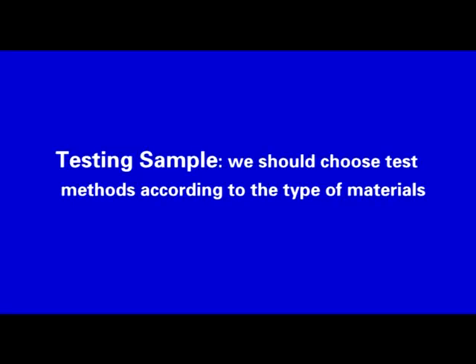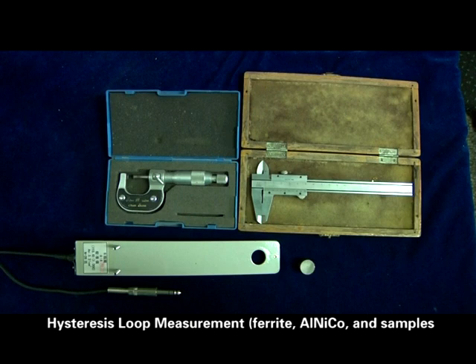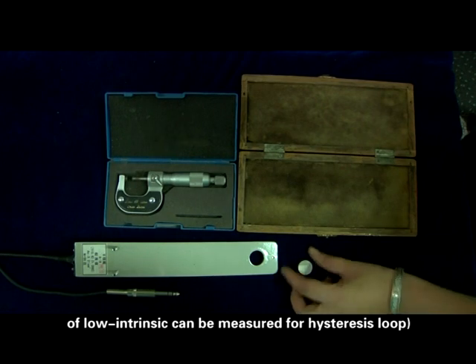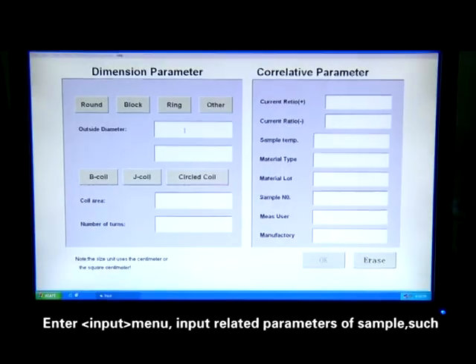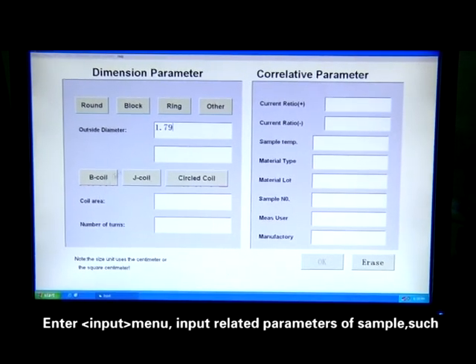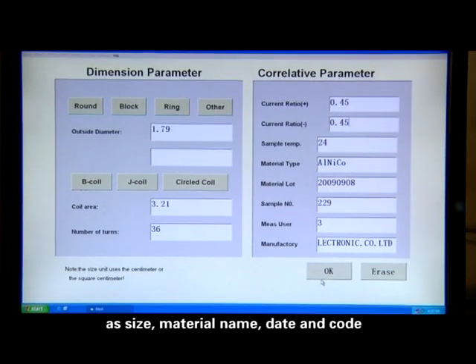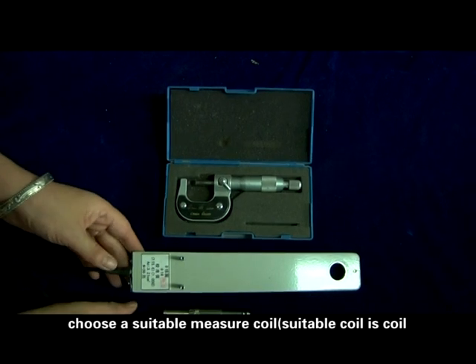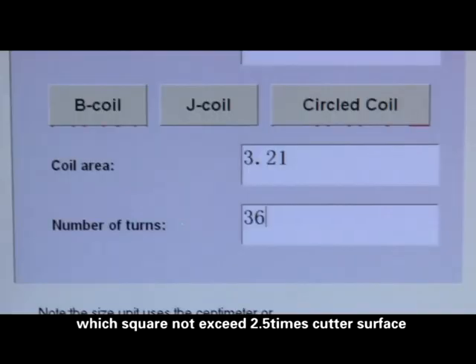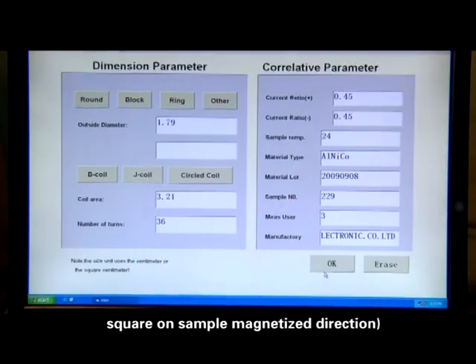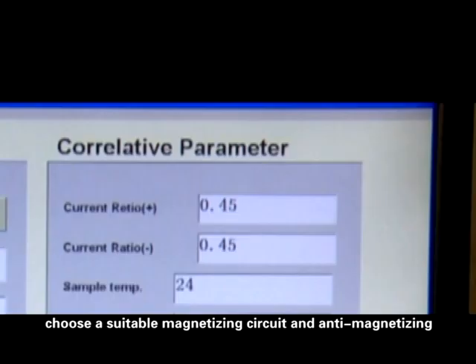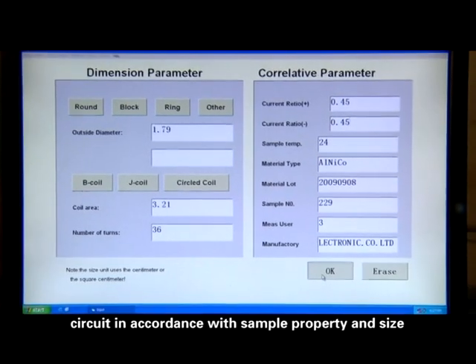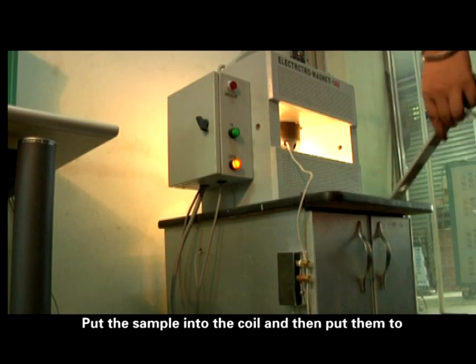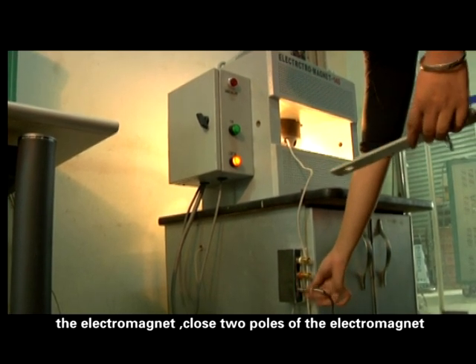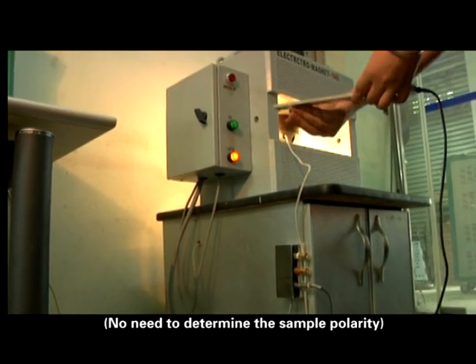Testing sample. We should choose test methods according to the type of materials. Hysteresis loop measurement. Ferrite, AlNiCo, and samples of low intrinsic coercivity can be measured for hysteresis loop. Enter input menu. Input related parameters of sample, such as size, material name, date, and code. Choose a suitable measure coil. Suitable coil is coil whose square does not exceed 2.5 times cutter surface square on sample magnetized direction. Choose a suitable magnetizing circuit and anti-magnetizing circuit in accordance with the sample property and size. Put the sample into the coil and then put them into the electromagnet. Close 2 poles of the electromagnet. No need to determine the sample polarity.